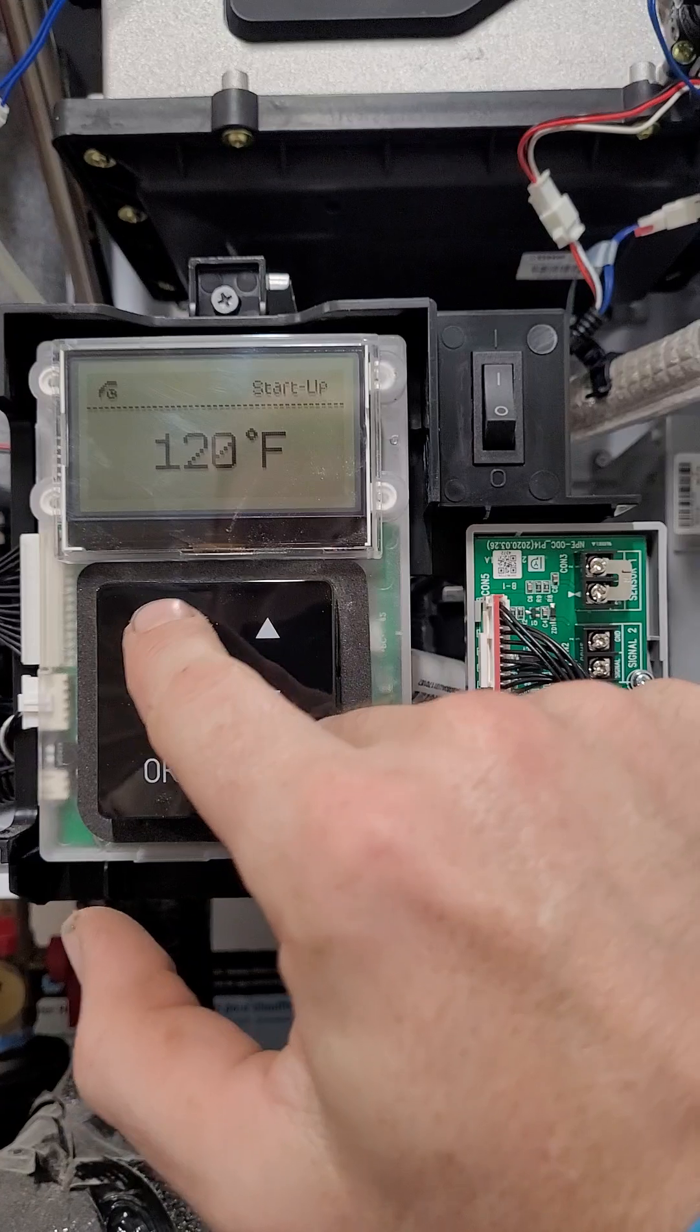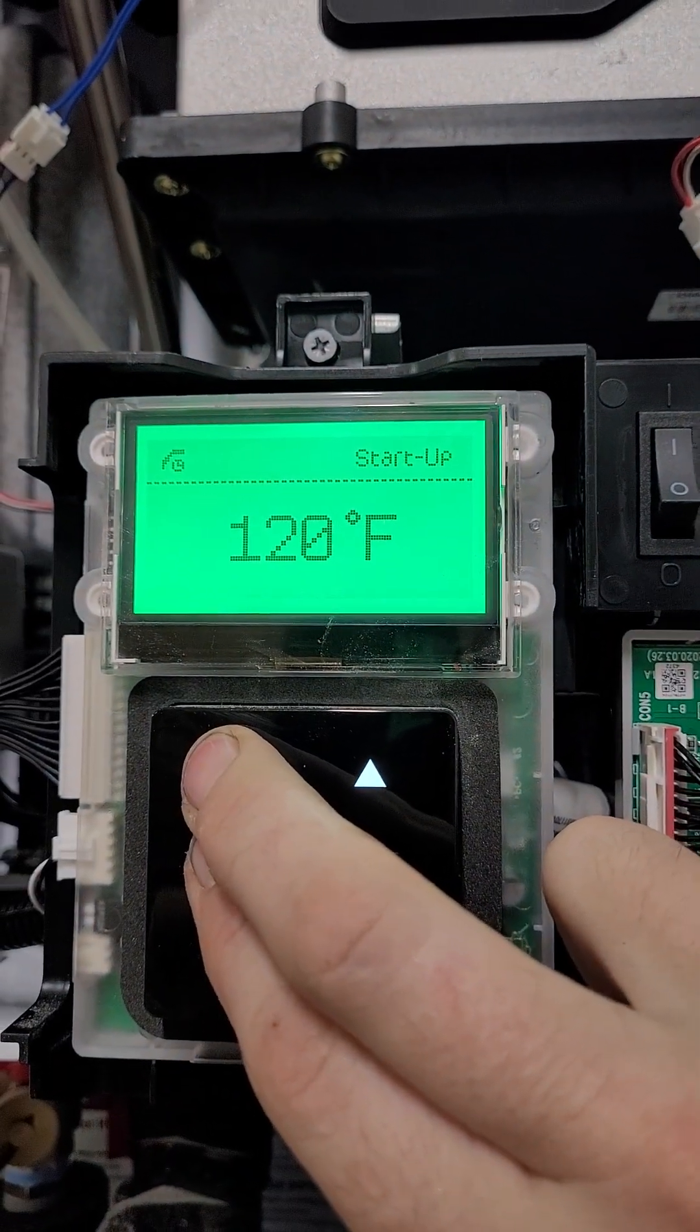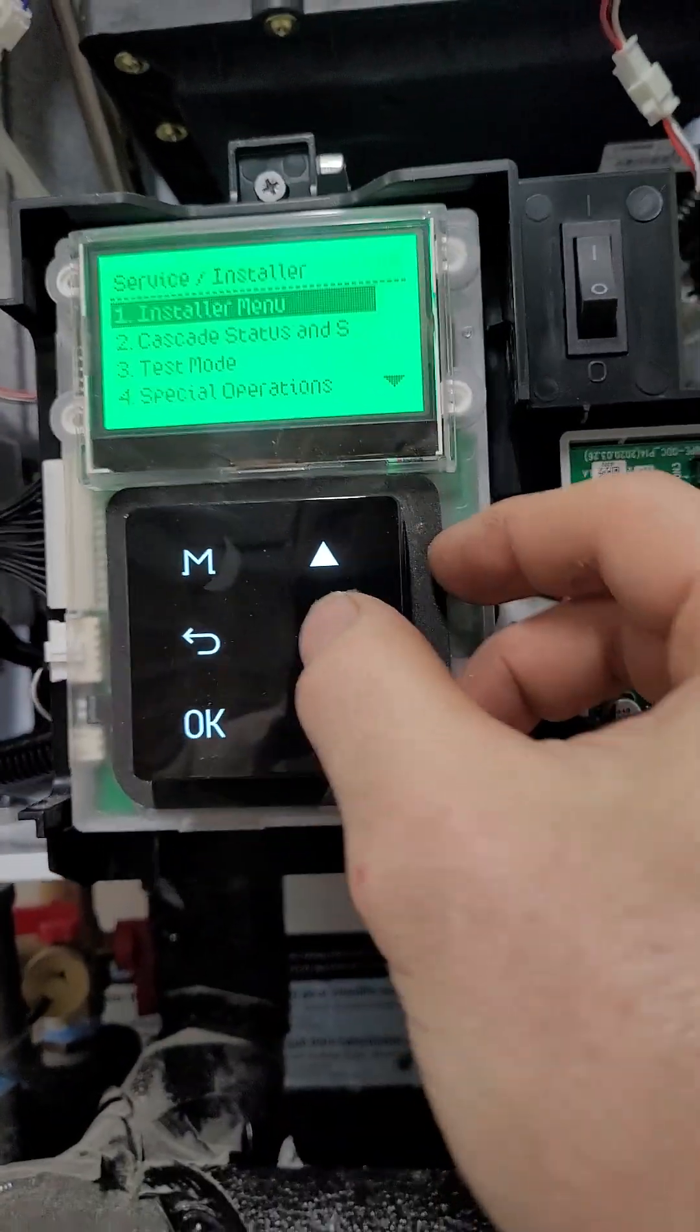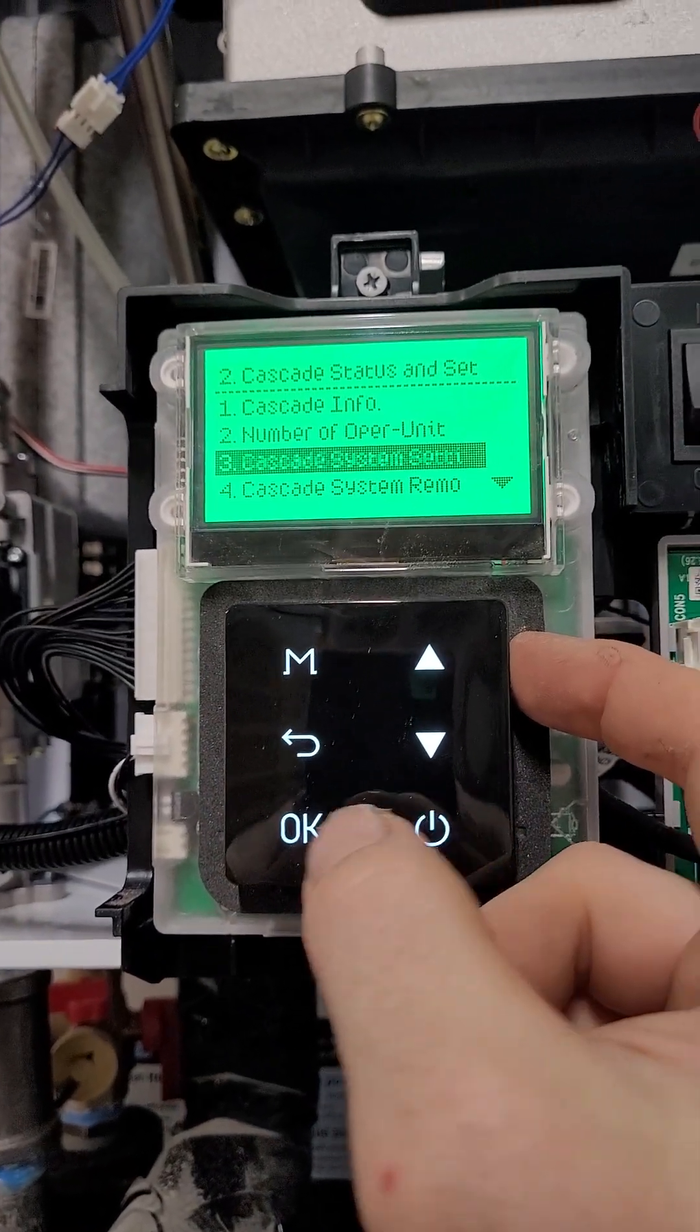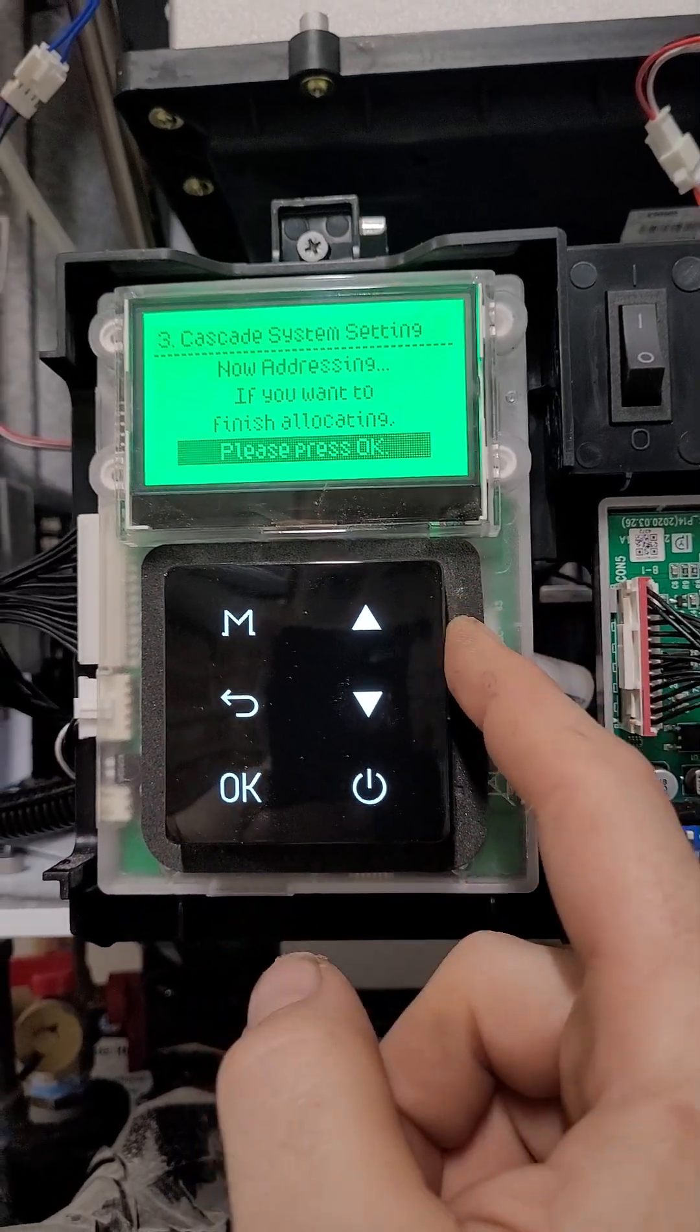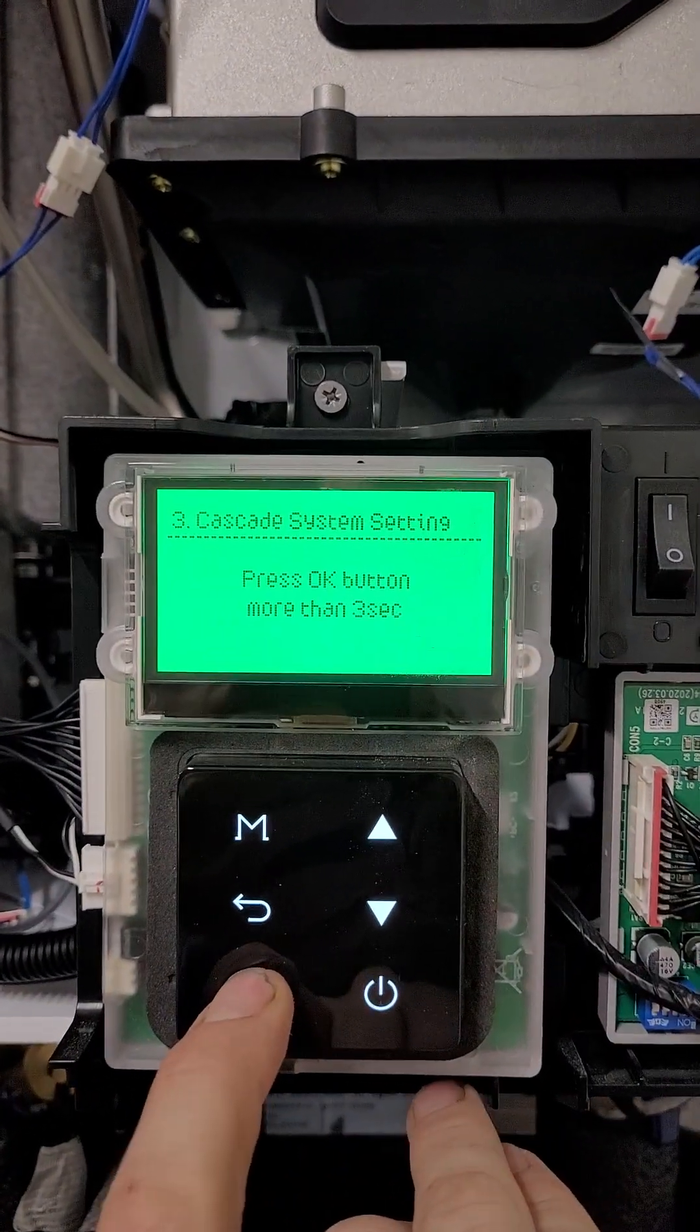We're going to press the menu and the back button at the same time. Now we're going to go to cascade status number two. We're going to go to number three. Cascade system settings. And we're going to begin. Now we're going to addressing. Obviously we did it on this one. So this is going to be the master. We're going to press okay over here.